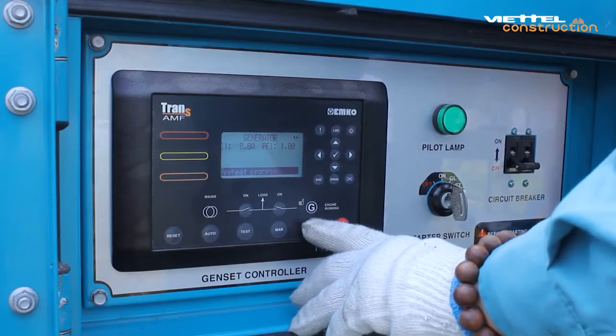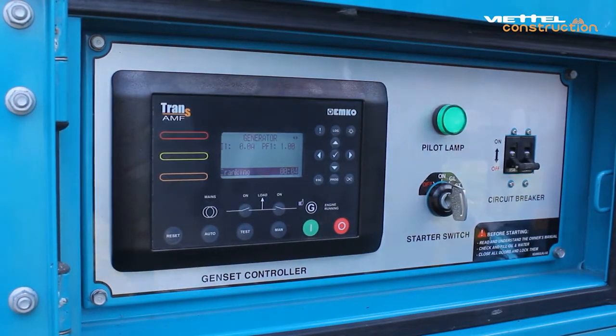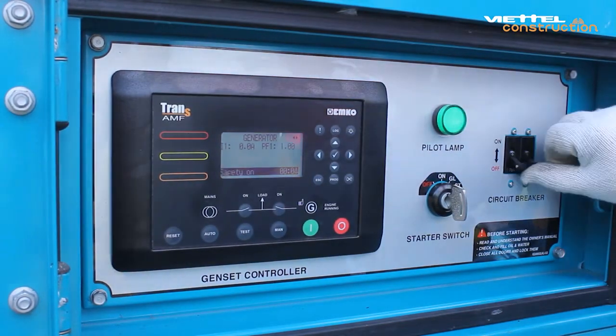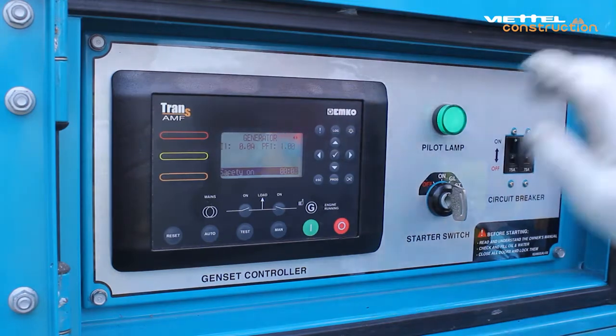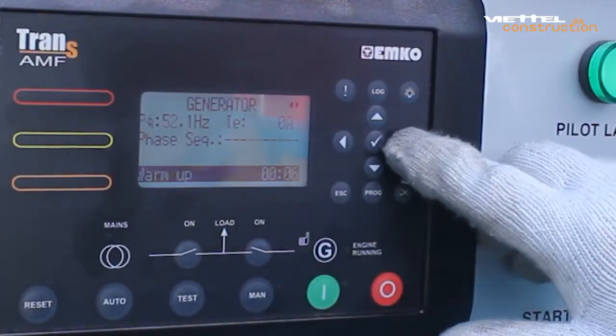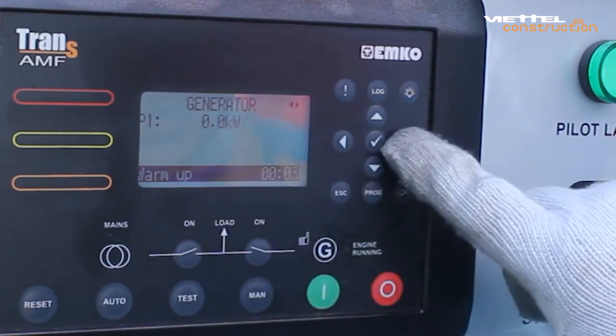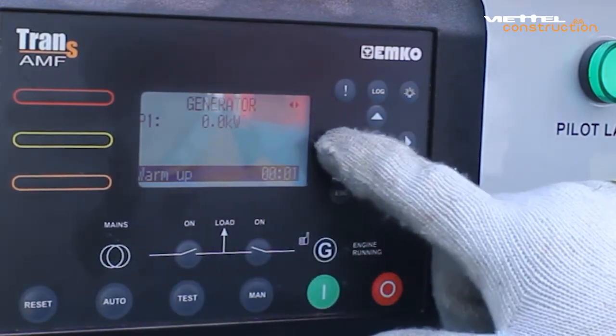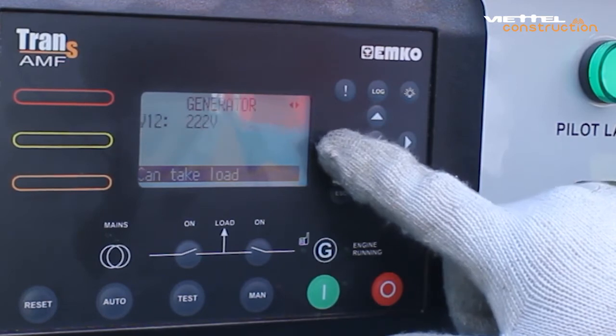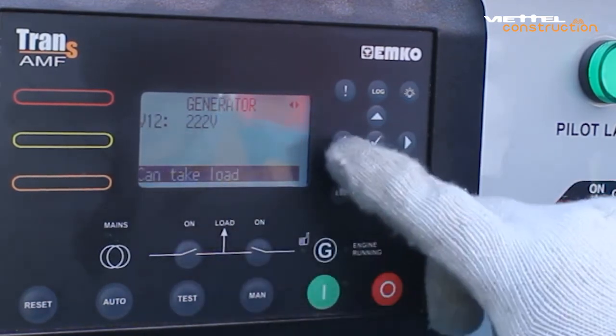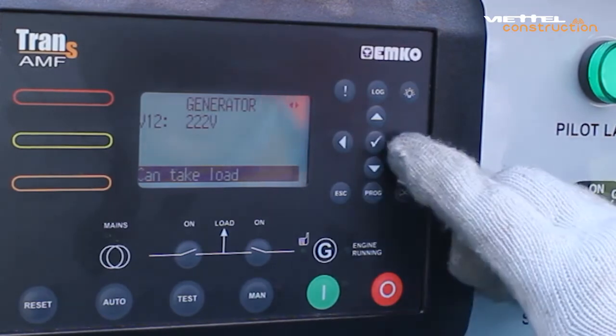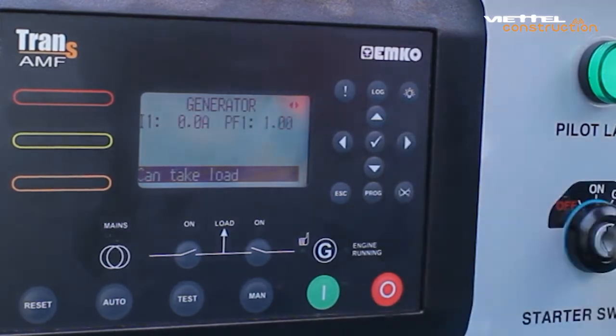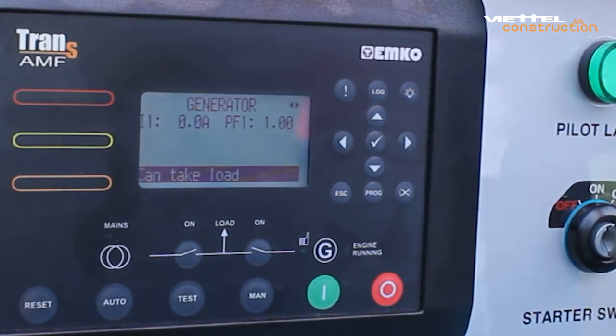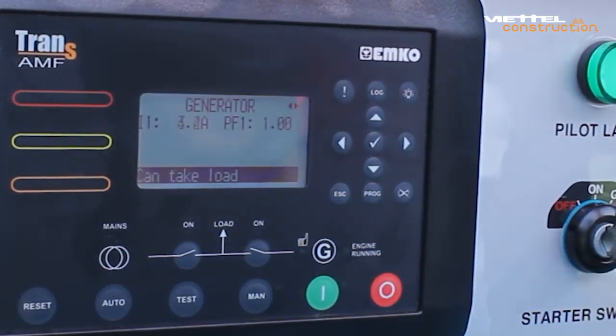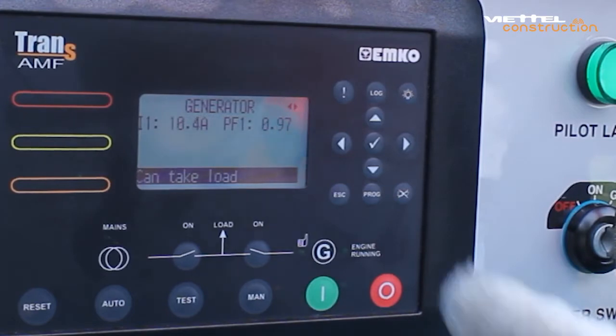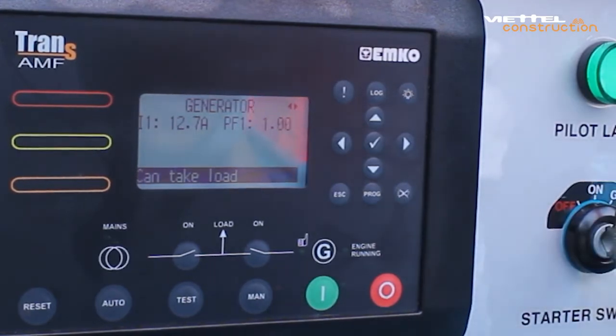After performing maintenance, test generator when in the state of no load and when in the state of 100% capacity of the machine. Measure. Check the parameters of voltage equal to 220/380 plus or minus 2.5%, frequency equal to 50 Hz plus or minus 5% and when in the state of 90% capacity of the machine. Clean up the scene after the maintenance, recorded in the test records.